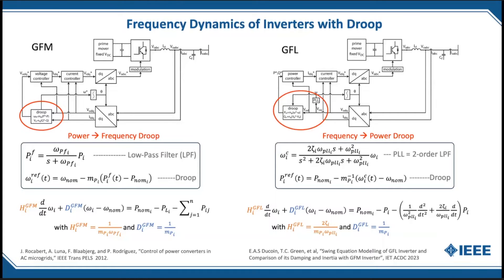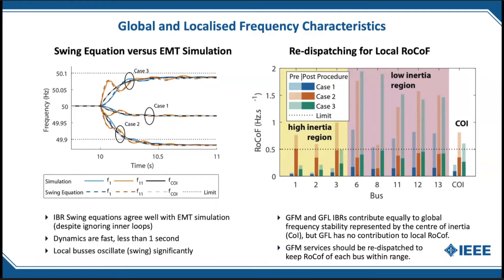We can combine these sets of resources and synchronous machines into overall swing equations. We tested this in the IEEE 14-bus system where synchronous machines have been replaced by grid-following and grid-forming inverters. On the left-hand side is a comparison between the swing equations and an EMT simulation for two loss-of-infeed events and one load rejection. The center of inertia — the weighted average of the frequencies — is shown as the black line: solid for simulation, dashed for the swing equation, and they correspond quite well.